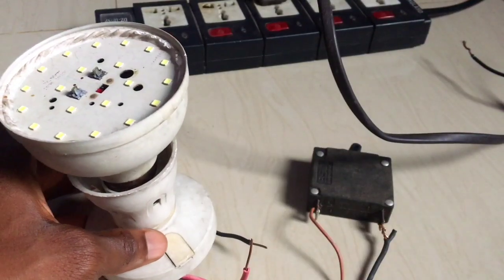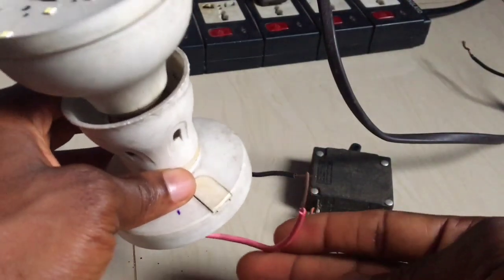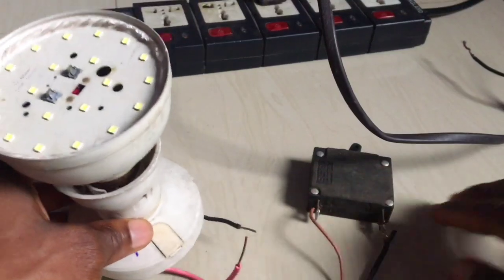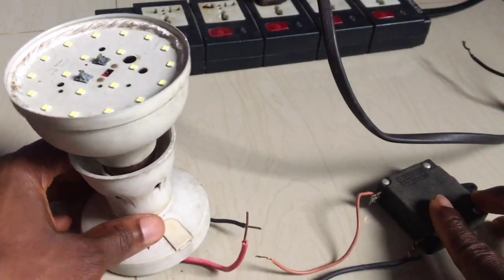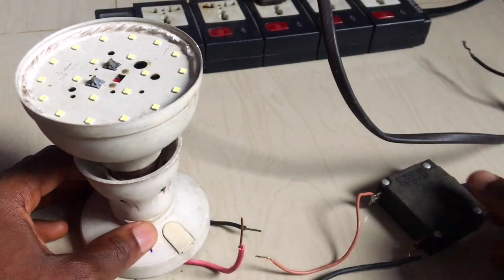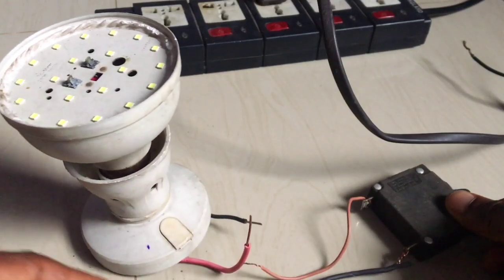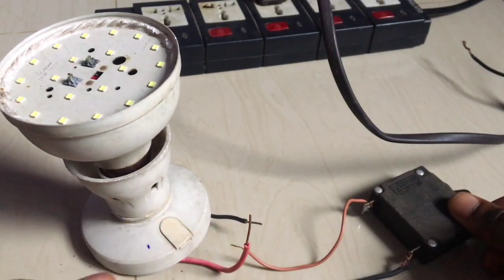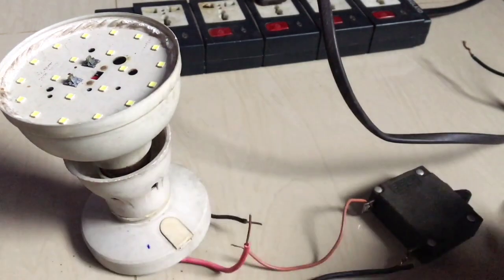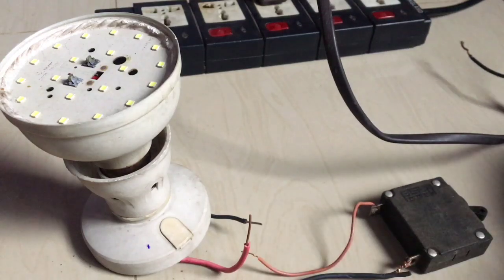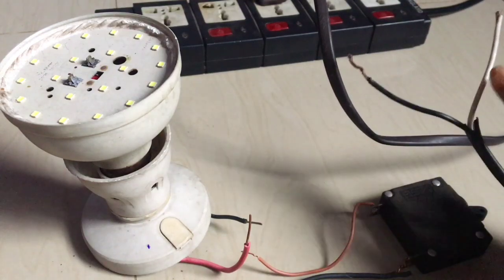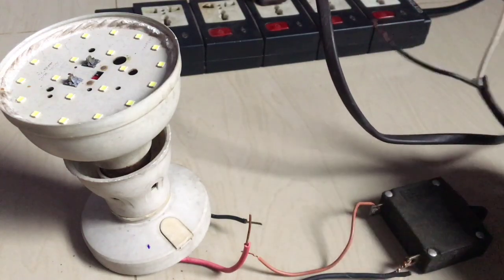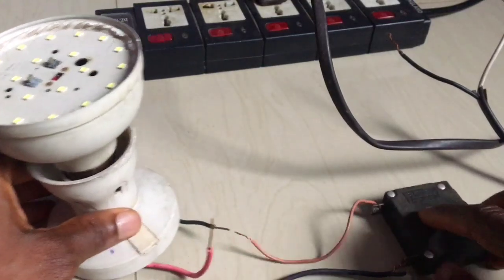So for surface wiring, this is a lighting point. We have the live terminal and the neutral terminal. For surface wiring, you can see black at your switch point. That is why I used a black cable here, but this black is not neutral. We are going to find out as we move on. Then we have our supply. This white is our live and this black is our neutral. So let's see how this connection goes.